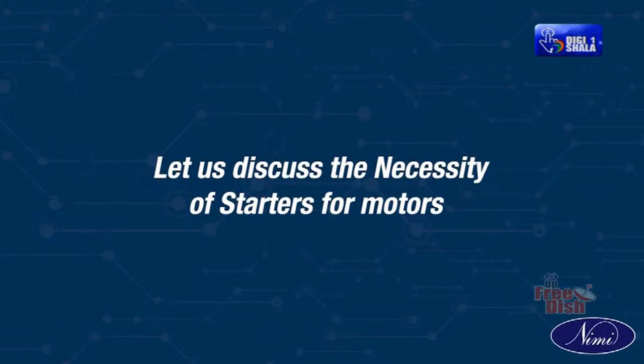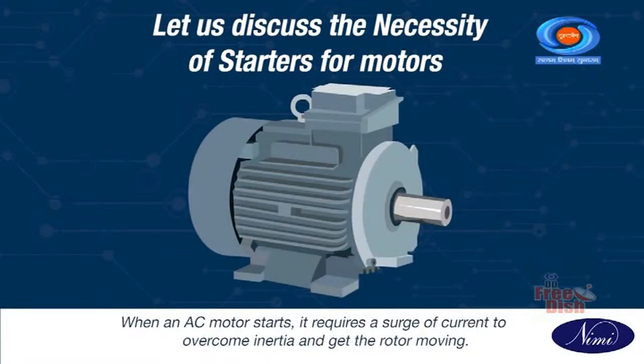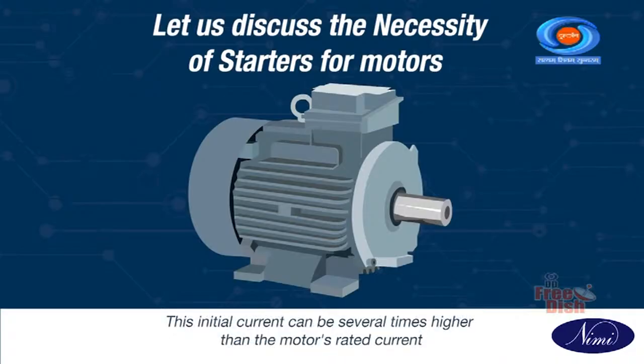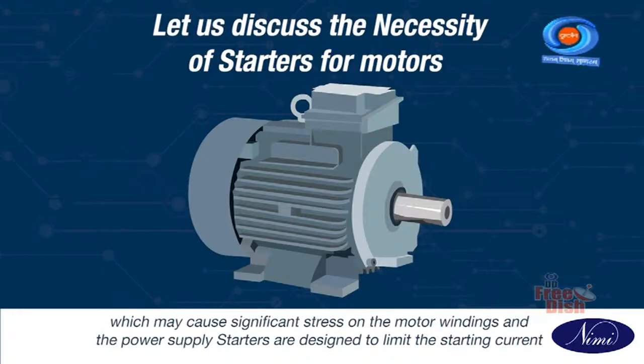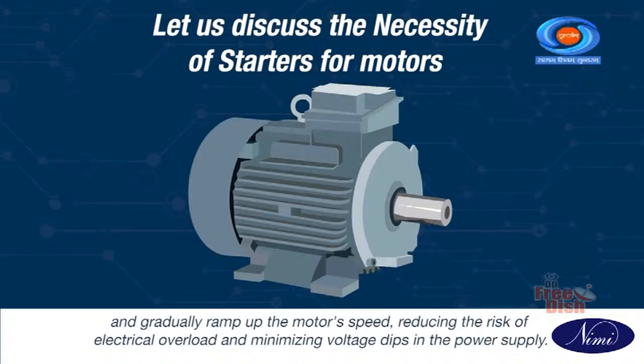Let us discuss the necessity of starters for motors. When an AC motor starts, it requires a surge of current to overcome inertia and get the rotor moving. The initial current can be several times higher than the motor's rated current, which may cause significant stress on the motor windings and the power supply. Starters are designed to limit the starting current and gradually ramp up the motor's speed, reducing the risk of electrical overload and minimizing voltage dips in the power supply.